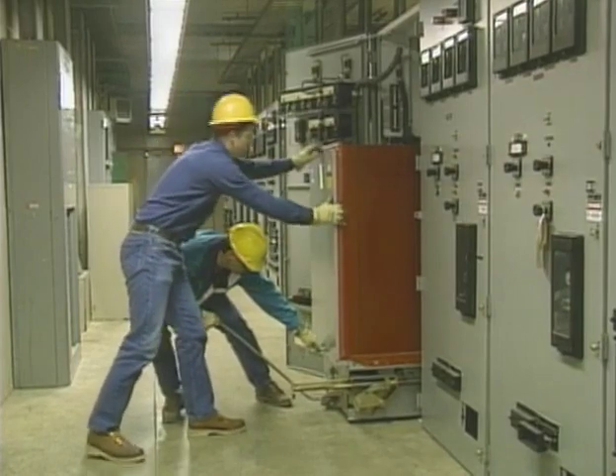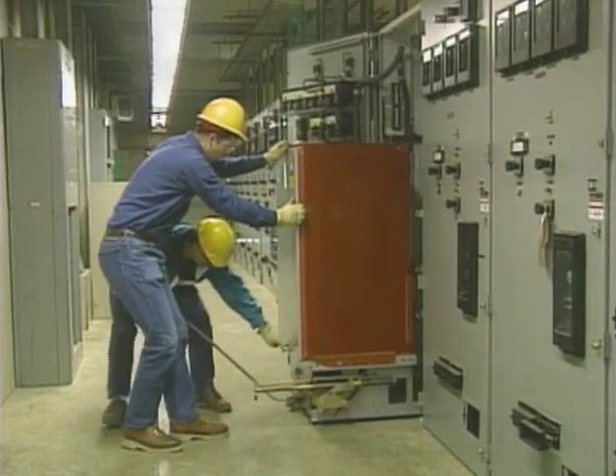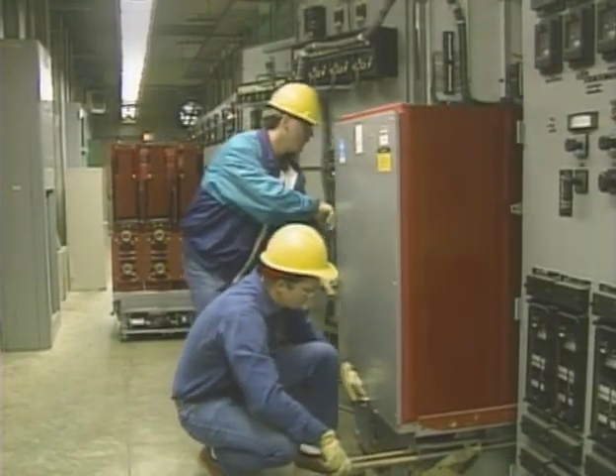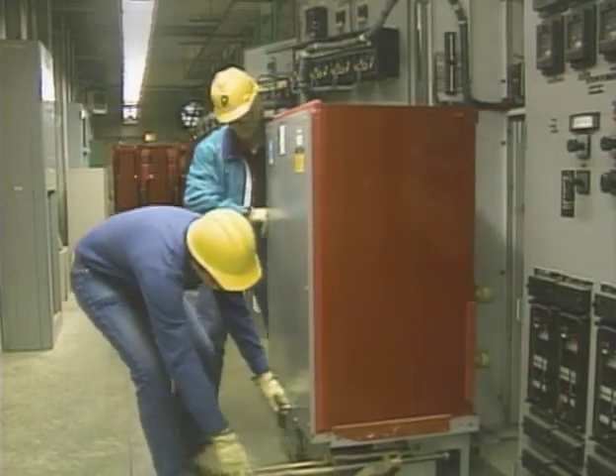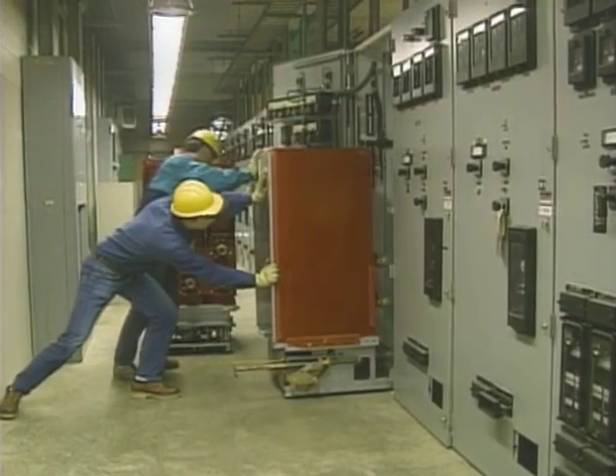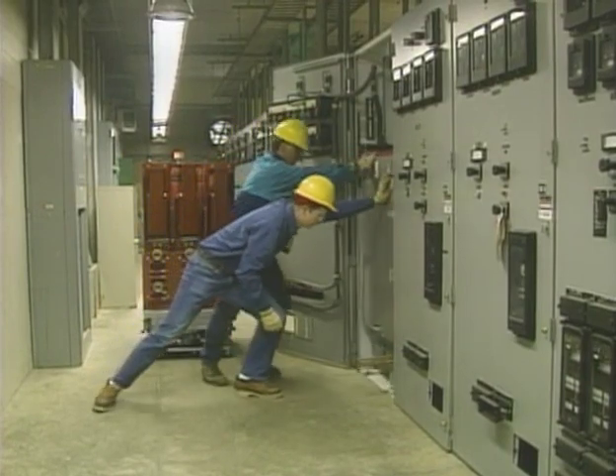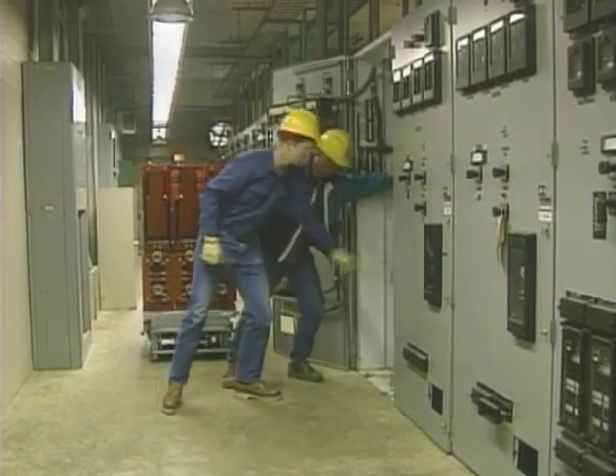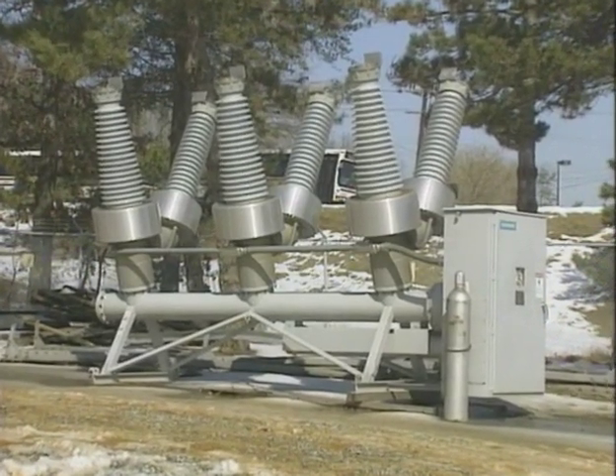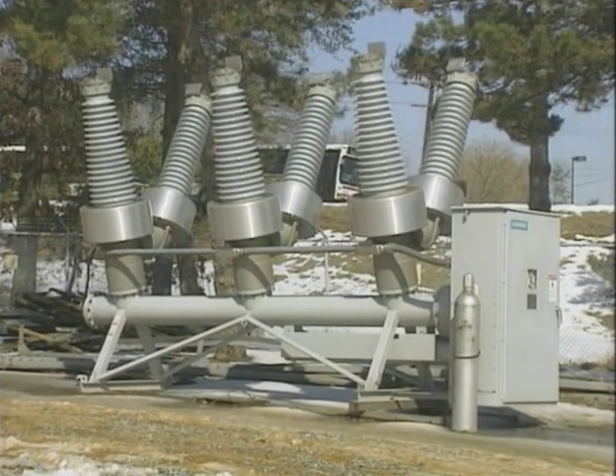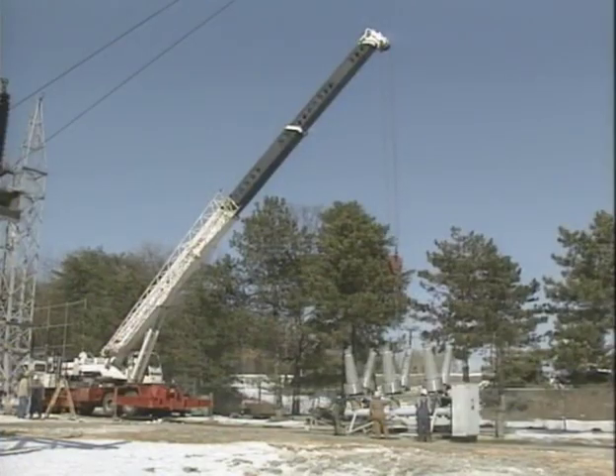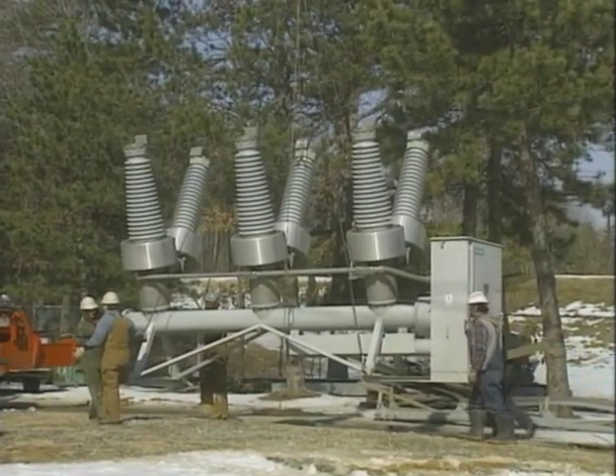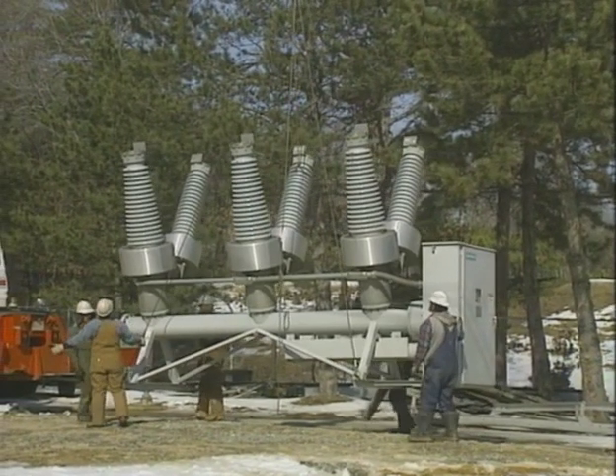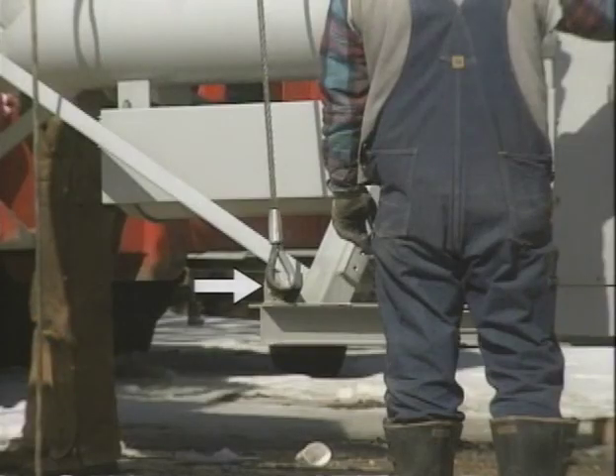Some breakers, such as draw-out type air magnetic or vacuum breakers, require very little in the way of installation. Typically, these breakers and their enclosures are designed so that the breakers can be interchanged. Wheels on the breakers and a portable fifth wheel make it possible for one or two people to remove or install a breaker as needed. Other breakers, such as this gas puffer breaker, require more planning and care to move and install. A breaker like this one is usually moved by lifting it, using slings and a crane. The slings are typically connected to eye bolts or lifting hooks on the breaker that are provided specifically for lifting.